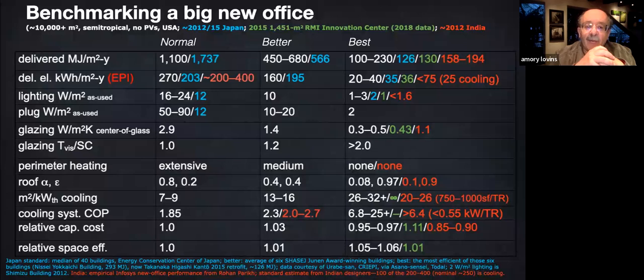So best US practice in the right-hand column in white cuts total and electrical needs, the first two rows, by 5 to 10-fold. The as-used lighting power density by 5 to 24-fold in the third row, plug loads by even more. Glazings insulate better by an order of magnitude. They become almost perfectly selective in sorting light from heat. Add super insulation, which isn't even shown here, and a heat rejecting roof, and you need 3 to 5 times less cooling per square meter. Then you can make the cooling system about 4 to 13 times more efficient, or just get rid of it. Mechanical savings help reduce capital costs by several percent and use the floor space about 1 to 6 percentage points more efficiently. Whatever exists is possible, and efficiency is a business opportunity. Rinse and repeat.